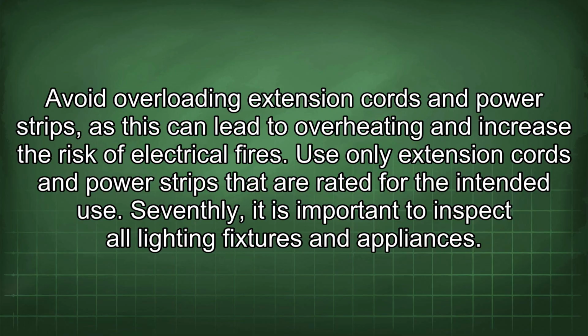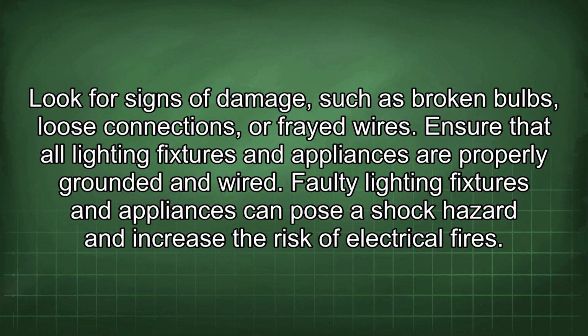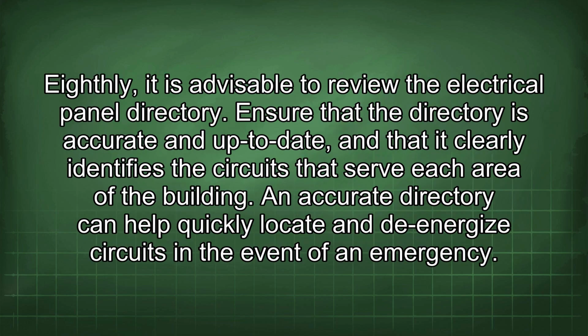Seventhly, it is important to inspect all lighting fixtures and appliances. Look for signs of damage, such as broken bulbs, loose connections, or frayed wires. Ensure that all lighting fixtures and appliances are properly grounded and wired. Faulty lighting fixtures and appliances can pose a shock hazard and increase the risk of electrical fires. Eighthly, it is advisable to review the electrical panel directory.